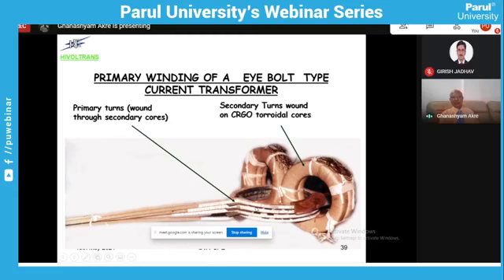It is reinforced in such a fashion that if the short circuit forces are passing through it, even 100 kiloamperes, say, the mechanical forces will not collapse this winding and will avoid any short circuit between the turns. So that is how the primary has to be designed and done properly.